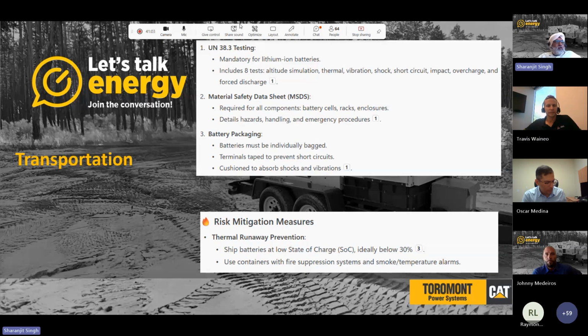What is the state of charge on these batteries prior to shipping? With these batteries, you can move them at any state of charge. Since you have a generator on the same trailer, you can move them at a lower state of charge, but based on test results, there's no requirement for a specific state of charge to ship them at. Some recommend shipping below 50% or 30% state of charge to reduce thermal runaway risk, but since this is thermally safe at the cell level, that requirement doesn't apply to the LTO chemistry we've got on this unit.